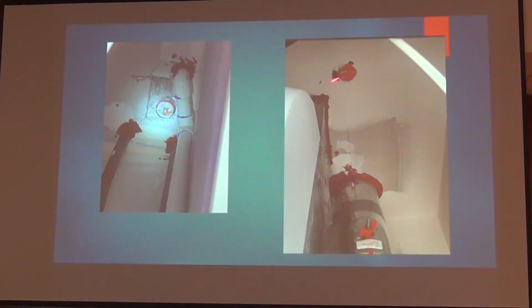Okay, that's a construction cover. Grab it with your thumb, give it a twist, and it pulls off. The sprinkler head should be there, and it should be clean. No paint is allowed. They are not allowed to clean paint off sprinkler heads, period. The only thing you clean off a sprinkler head is drywall dust. Blow it off. Don't hit it with a rag.